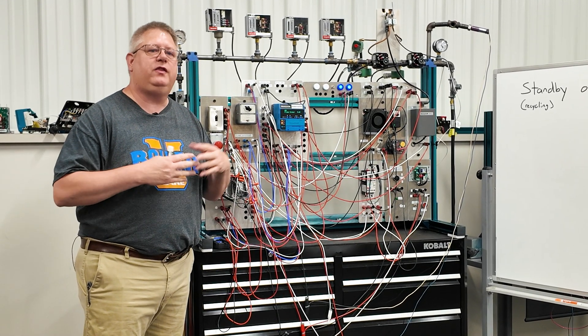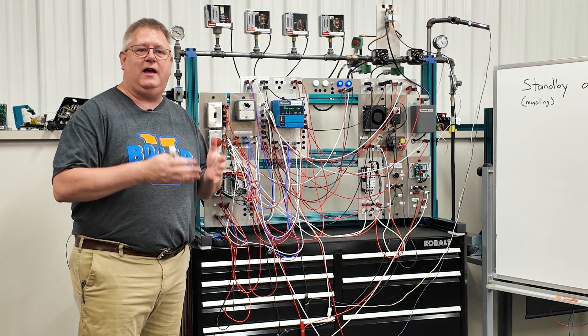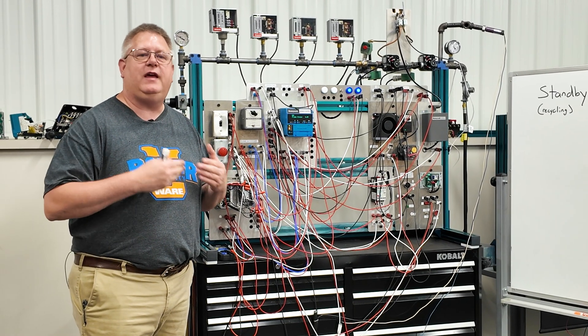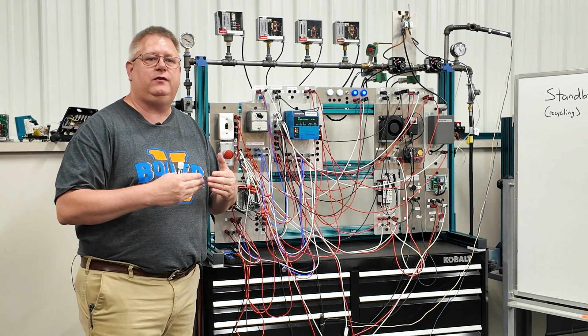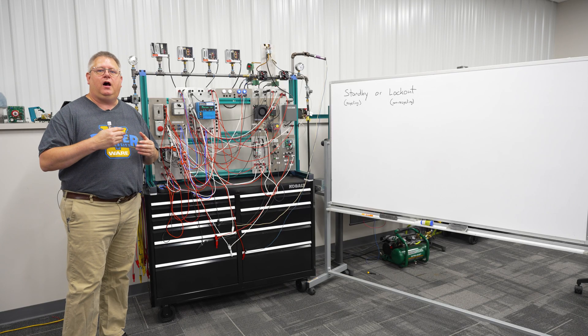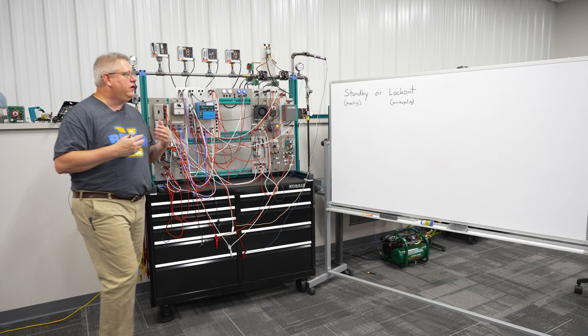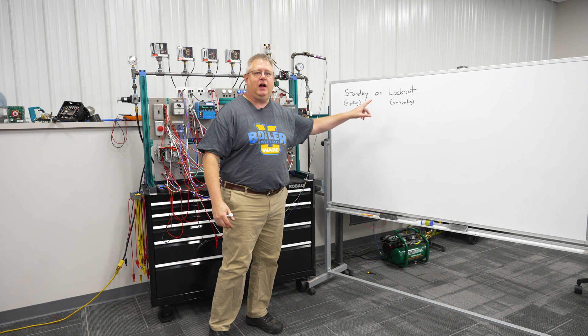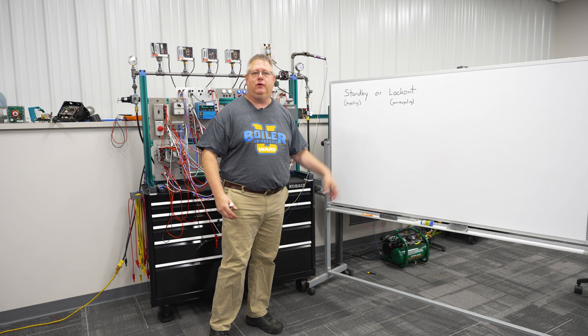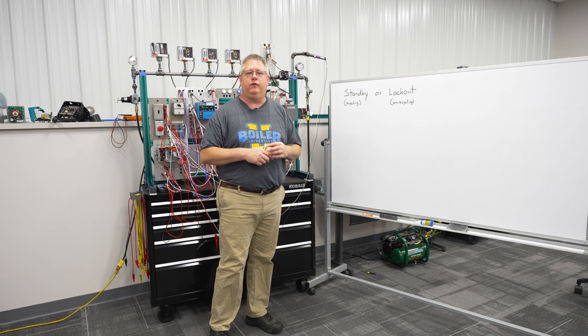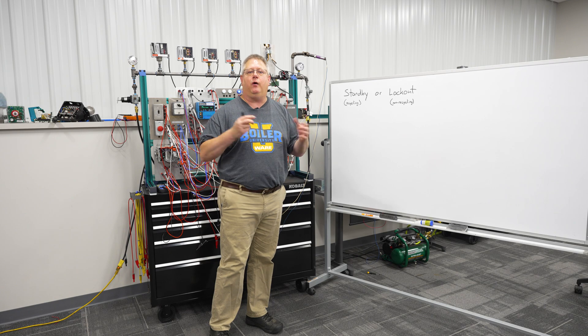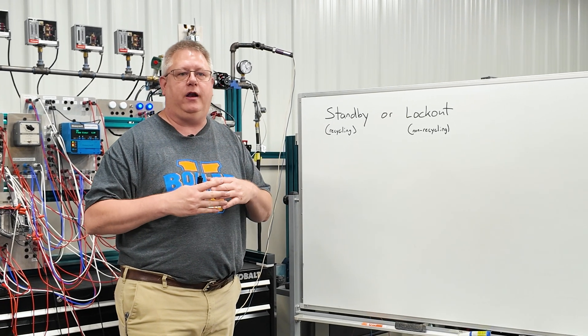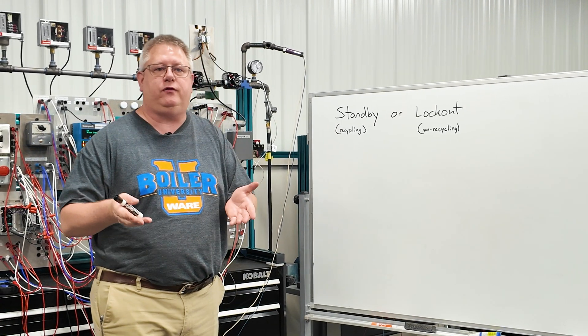One thing that we can do is test limits, which we need to do anyway. But when we test those limits, make notes — because there are essentially two limit circuits that constitute 90% of our boiler failures: we're out on a gas pressure switch or we're out on an operating pressure switch.